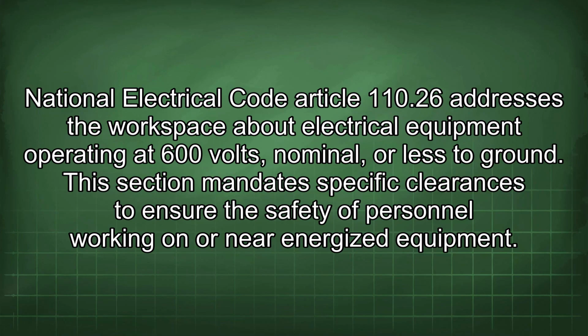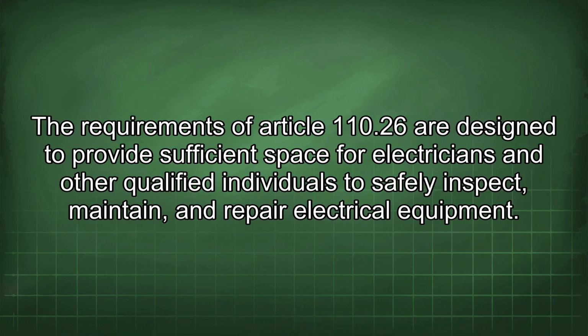National Electrical Code Article 110.26 addresses the workspace about electrical equipment operating at 600 volts, nominal or less to ground. This section mandates specific clearances to ensure the safety of personnel working on or near energized equipment. The requirements of Article 110.26 are designed to provide sufficient space for electricians and other qualified individuals to safely inspect, maintain, and repair electrical equipment.